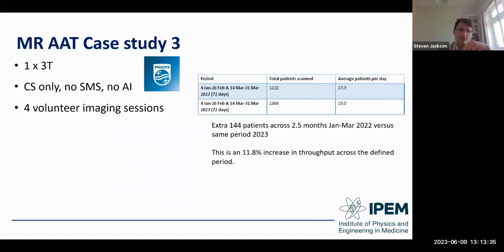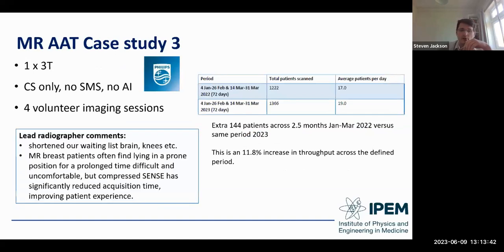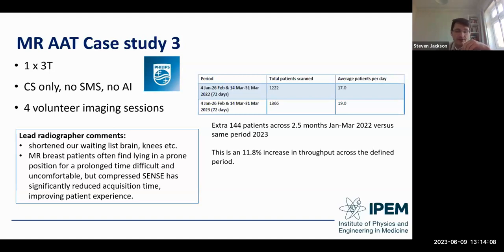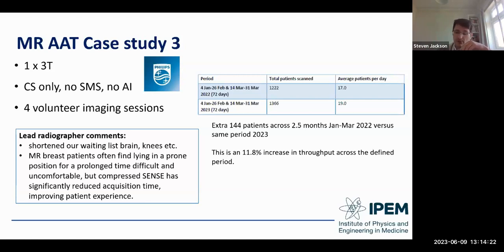A hospital with one Philips 3T with a Compressed Sense license — no SMS, no AI — ran four six-hour volunteer imaging sessions. After implementing new protocols and reducing imaging slot times, they were able to scan an additional two patients per day, comparing the first quarter of 2022 with the first quarter of 2023, equating to an 11.8% increase in throughput. Comments from the lead radiographer: they are ahead on their waiting list for brains and knees. A specific example: breast patients who find lying prone for prolonged periods very difficult have benefited significantly, as Compressed Sense has reduced acquisition time and improved patient experience, especially for those returning annually for screening.